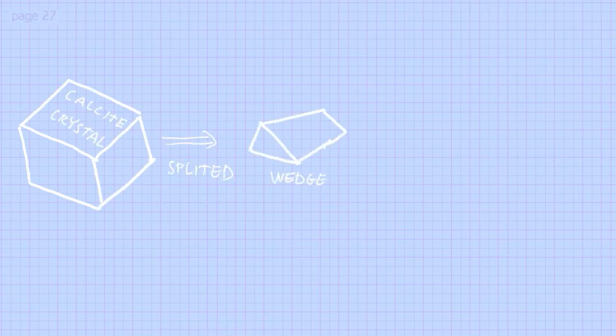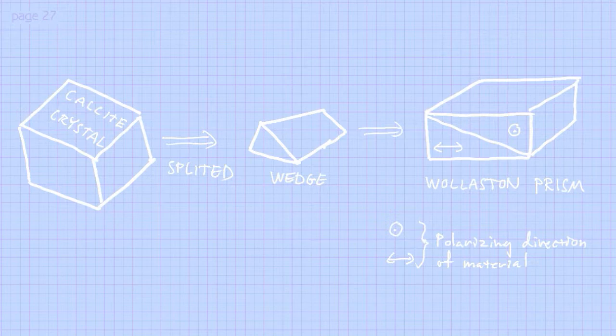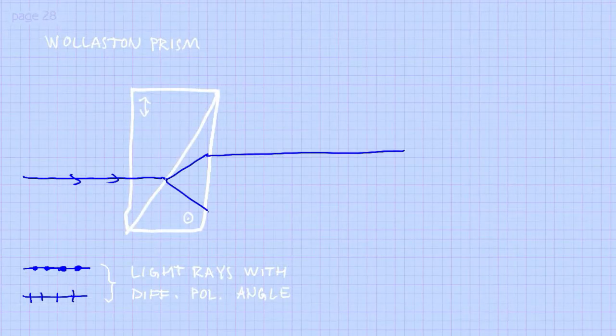So how do you transform this crystal into a usable differential interference contrast microscope? First you need to split this crystal into wedge-shaped forms, then combine two of these wedges into what's called a Wollaston prism. When you have made a Wollaston prism you actually create two of them. One you place above the light source beneath the condenser, and the other one is on top of the objective. The polarized light sent in from the light source goes through this crystal and is split up into two different pathways, giving two separated light waves.